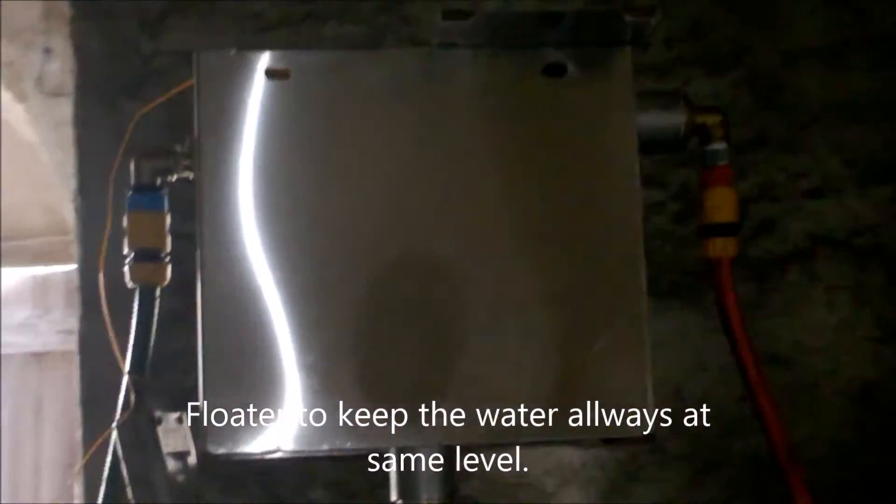The hottest water goes inside up there and then travels through the buffer tank and leaves for the gasifier again down there. Let's see what temperature we have now. The incoming water from the gasifier is 50 degrees Celsius.